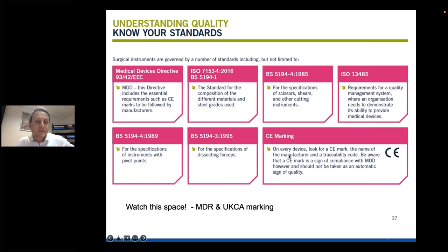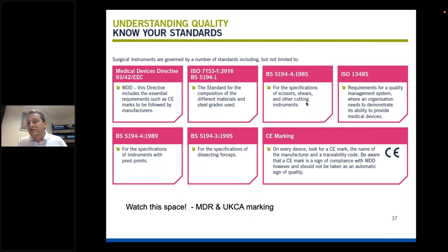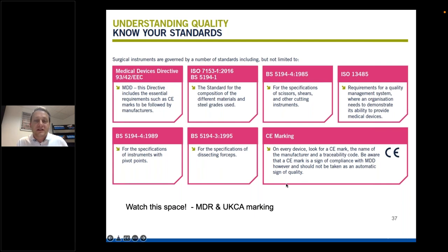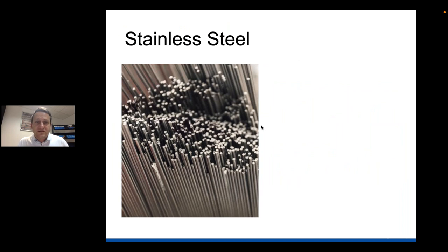Other standards worth mentioning: there are British Standards for surgical instrument making covering scissors, shears, dissecting forceps, and other instruments - detailing testing materials and methods. There is also a German DIN standard which is more detailed than the British Standard and cites particular test materials. Then of course there's the regulation: the Medical Device Directive, now superseded by the MDR in Europe. In the UK we're still working to the MDD, but watch this space for UKCA marking, which will be taking effect on surgical instruments.